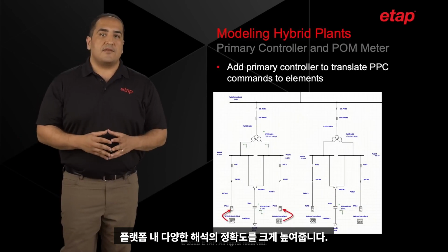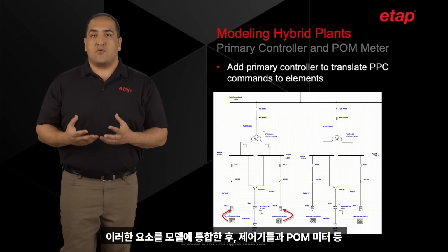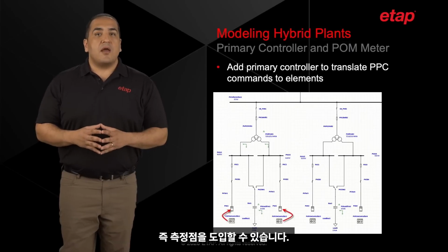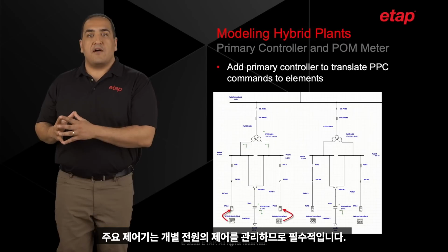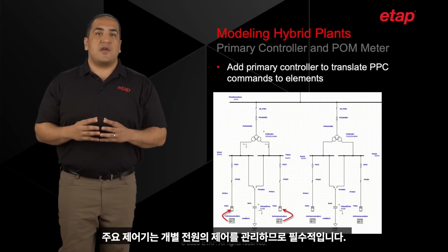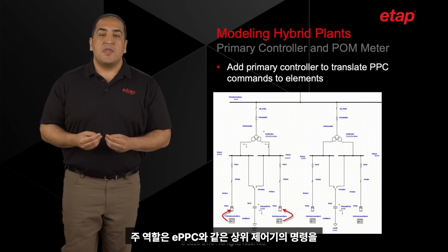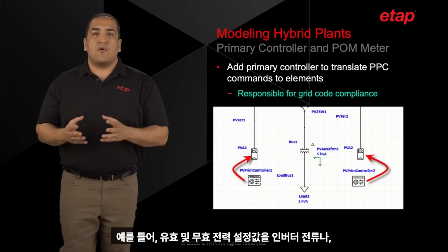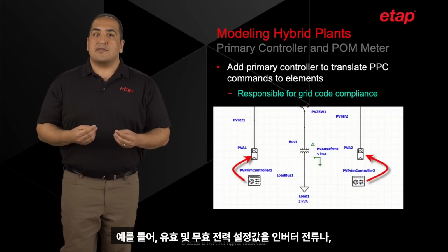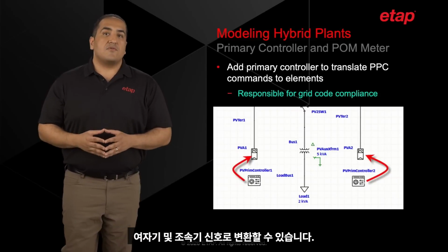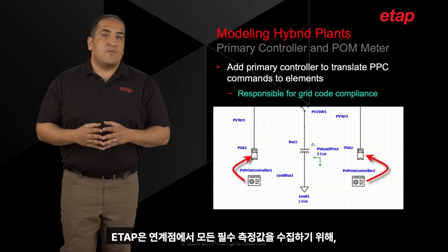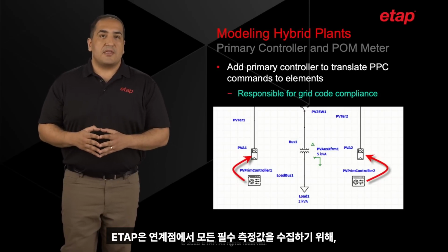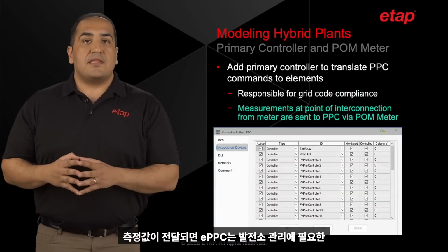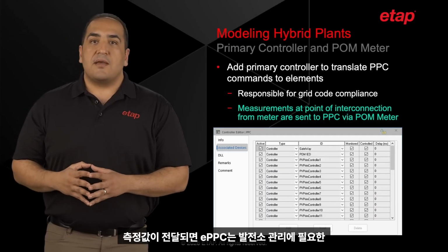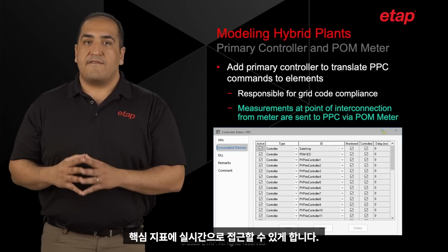After integrating these elements into the model, primary controllers and the point of measurement or POM meter can be introduced. Primary controllers are essential as they manage the control of individual power sources. Their main role is to translate commands from secondary controllers like ePPC into actionable control signals for electrical components. For example, they might convert active or reactive power set points into inverter currents or exciter and governor control signals. ETAP also provides a unique controller for the POM meter, which is needed for collecting all necessary measurement at the point of interconnection. This data then is passed to ePPC, ensuring that it has real-time access to vital metrics needed to manage the power plant effectively.